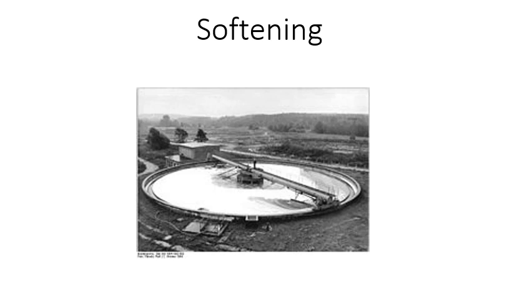for pH control. Treatment chemicals that will raise the pH and alkalinity of water, making it basic: calcium hypochlorite, which is a disinfectant. Sodium hypochlorite, bleach, for disinfection. Sodium hydroxide, caustic soda, which is used in softening. Sodium carbonate, which is soda ash, also used in softening. And sodium aluminate, which is used in coagulation and flocculation.